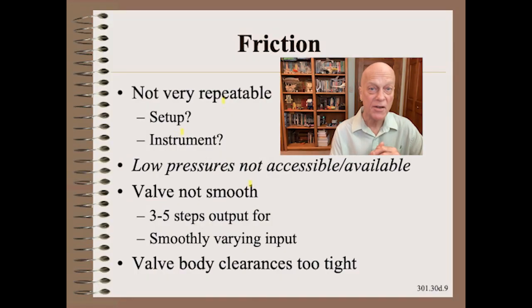This story is about friction. It begins by noting that the calibration or performance is not repeatable. You will also observe that low pressures are not accessible and are not available. However, you need to take it one step further to determine if it is your test that is not repeatable or some component of the system that is not repeatable, and if so, which one is it?